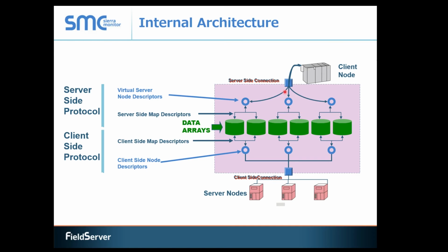So we start by defining a connection again. In this case it's an Ethernet connection, so our two Ethernet ports available in FieldServer are N1 and N2 on some hardware platforms, and so we may declare N1 as an Ethernet port and a BACnet server. And then our next step would be to declare device instances for BACnet to come and fetch. So in BACnet, device instances are the equivalent of station addresses in Modbus.